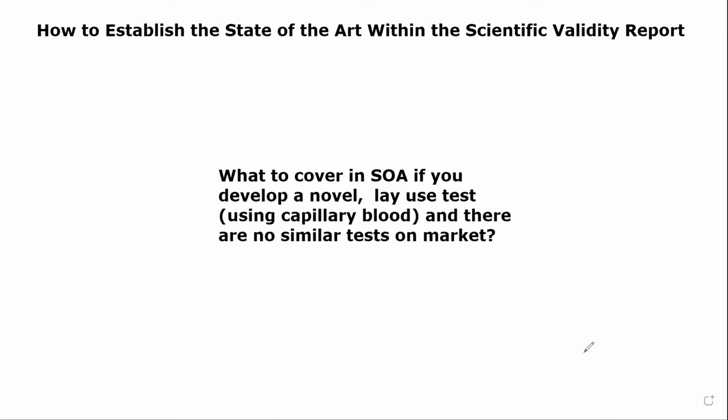So you can't say I don't have any competitors and therefore I have no data. That's not going to be acceptable to the notified body. What you do need to do is establish the alternatives and rely on them more heavily, and rely on clinical practice guidelines when you're dealing with a novel analyte. That burden for establishing scientific validity can be a little bit higher because you need to show how this test and how the technology compares to existing technologies.